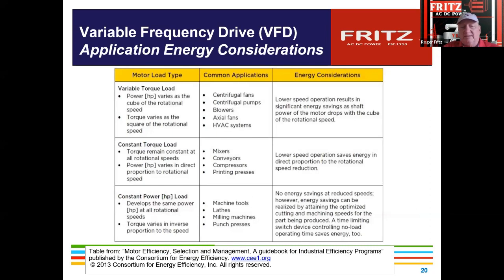Let's see. This is a sheet that talks about variable torque loads, constant torque loads, and then constant horsepower loads, where you really don't have too much opportunity. What they mean by that is a machine tool, a lathe, milling, punch presses and those things. There's really not a way other than, on a punch press, you may want to slow the cycles down, but you really can't do much speed control here. So it's got to stay constant horsepower. You don't see a lot of savings.